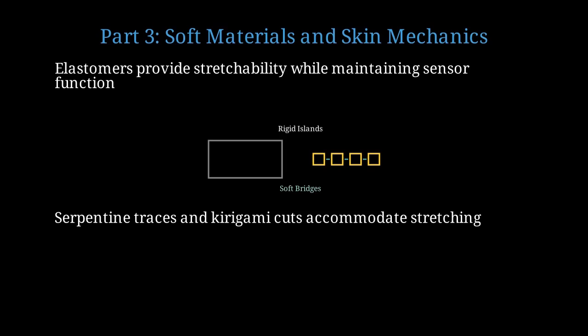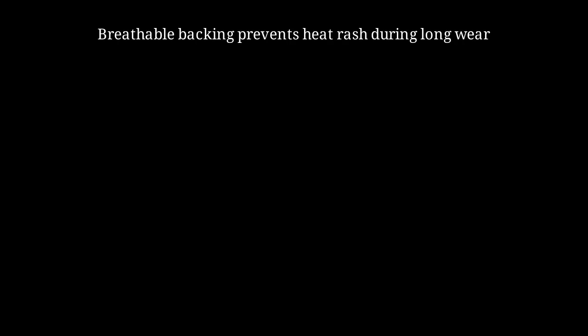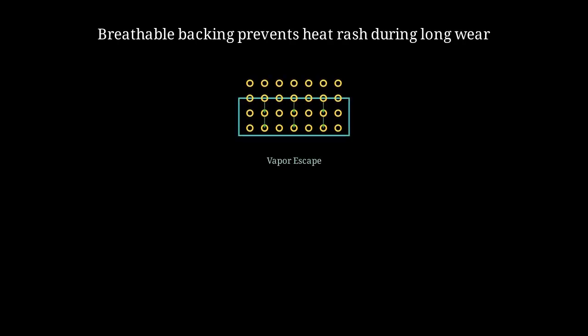Serpentine interconnects uncoil during stretching, maintaining electrical continuity while accommodating large skin deformations during activities like joint bending. Micro-perforated films and breathable laminates allow vapor exchange to prevent sweat accumulation and skin maceration during extended wear periods. Micropores allow water vapor to escape while blocking liquid sweat, maintaining thermal comfort and preventing skin irritation during multi-hour monitoring sessions.